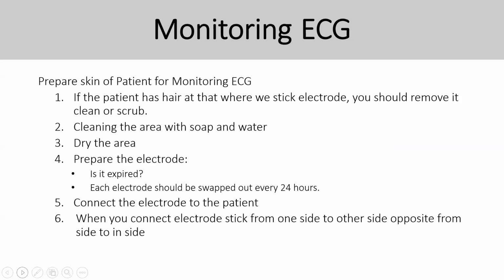So all this you need to know, because if the ECG gel is dry or not enough, you're not going to capture any reading, or the reading is not good enough. This is very important when you're preparing a patient with the ECG. Because sometimes the user is going to complain that the ECG reading is not good, but eventually you see maybe the ECG lead is overused or expired, or maybe sometimes with the ECG gel, you are not putting enough gel on the body.